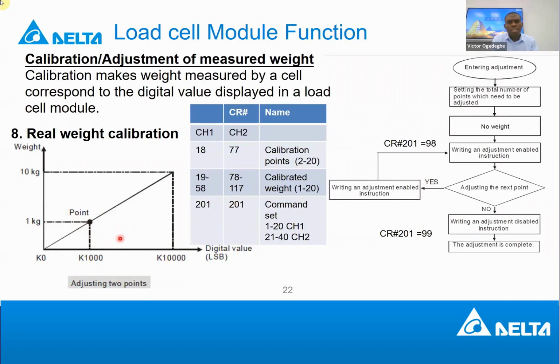It's possible to calibrate 20 points in case the tolerance of the sensor is not very strong, so what is coming from the sensor is not linear. You can calibrate several points and say, if I have this from this sensor, give me this digital value. So the load cell module will give you values based on what you have calibrated. It's like a trick. I can calibrate it so that if I read 1 kg, it gives me 10,000, because that's my calibration.